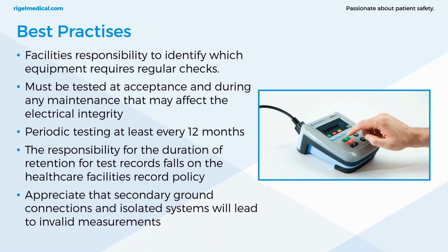There are also recommendations on the minimum periods for safety checks whilst in service, and this is at least every 12 months. But the responsibility for the duration of retention of test records falls on the healthcare facility's records policy. So with alternative equipment maintenance procedures, this can vary widely once you've got evidence on the safety and reliability of the devices that are in your workshop. So it's only up to the healthcare facility to decide this.